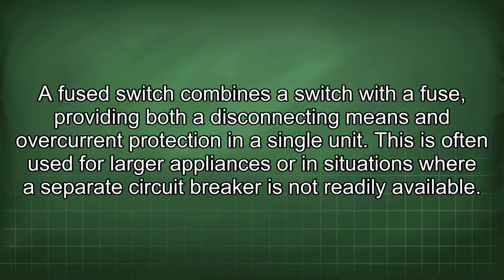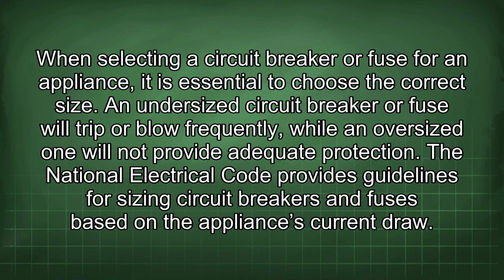This is often used for larger appliances or in situations where a separate circuit breaker is not readily available. When selecting a circuit breaker or fuse for an appliance, it is essential to choose the correct size. An undersized circuit breaker or fuse will trip or blow frequently, while an oversized one will not provide adequate protection. The National Electrical Code provides guidelines for sizing circuit breakers and fuses based on the appliance's current draw.